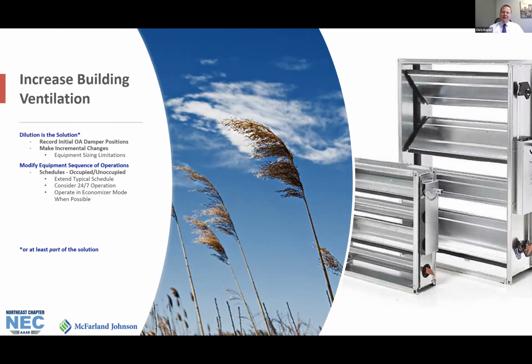So no, there's some spare capacity in the units I propose in the design. Most HVAC systems are not designed to see these large increases. So I recommend being very methodical about the changes to your outside air damper positions in your central equipment. Keep an eye out for extreme or extended abnormally hot or humid conditions, and don't hesitate to return to the original damper positions. It's recommended you modify your HVAC equipment schedules to increase the occupied periods, operate in economizer mode.